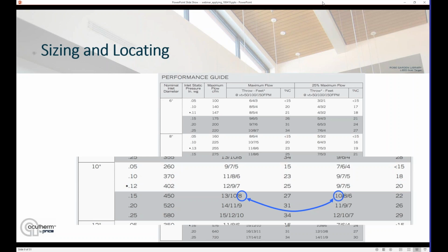My recommendation here is if you have to go a little bit closer to a wall, that's better than going a little bit further from a wall. My logic being that going a little bit closer to the wall means that when the diffuser is 100% open, you may have a little bit of velocity coming down that wall toward the occupants. But given this is the 100% open, that's your maximum load case, your design case, that's only going to happen a couple times a year. Where you spend the majority of the time is in a turn down condition. So we want to make sure that we are getting good mixing at all times. And so going a little bit closer to a wall is preferable to going a little bit further from a wall, in which case you might create less well-mixed rooms on the turn down case.